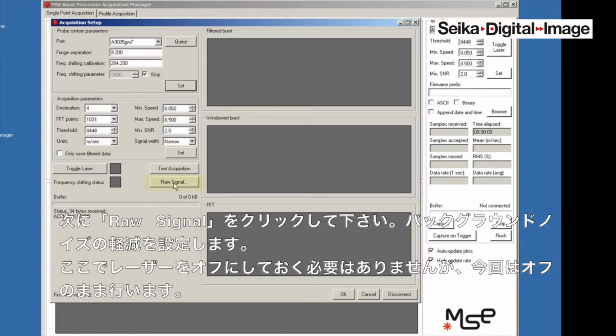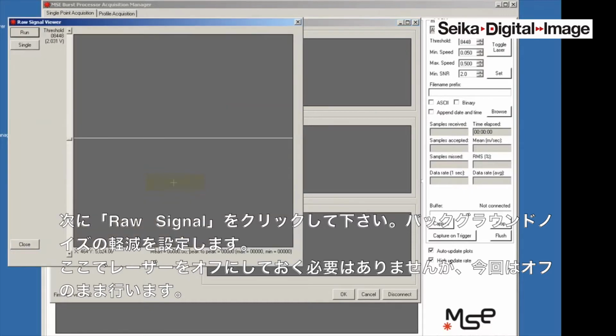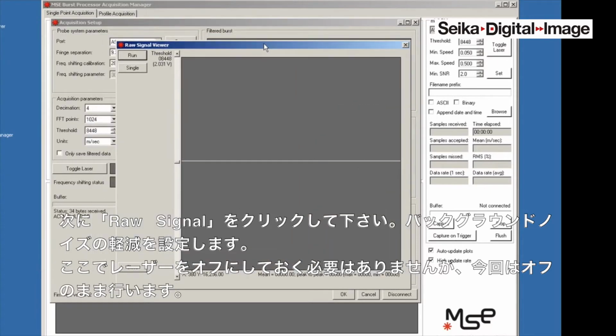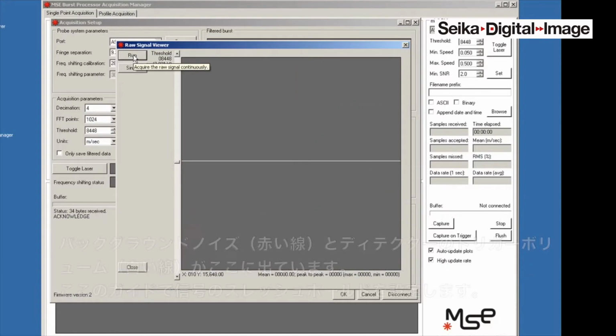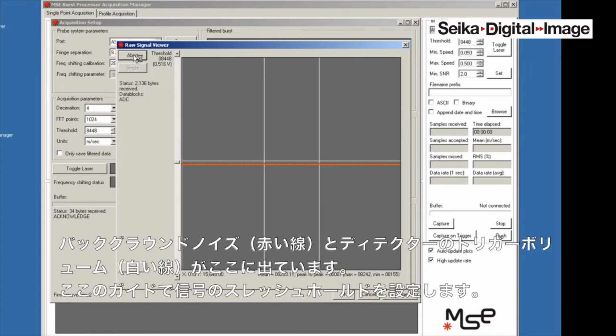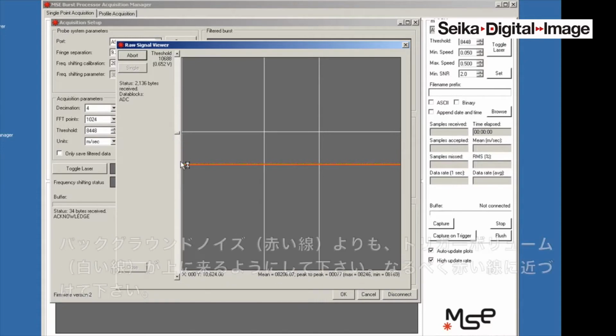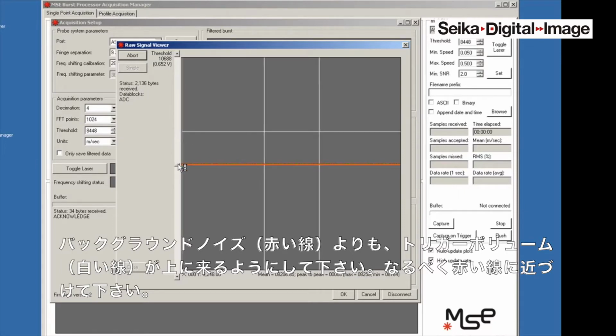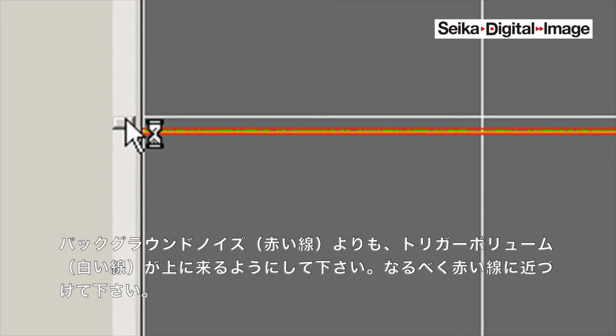First, what you need to do is push raw signal, and it's really raw background noise, with the laser off preferably. You don't have to have the laser off, but I prefer to have it off. When you run it, you will see where the background noise or background setup of the detection system is set, in terms of an arbitrary number in this case. This guide and this white line sets the threshold of your signal. What this says is that the background noise is in this range, and we expect the signal to be above that. So we will slide this down such that this white line that indicates the trigger value for the system is just above the background noise.